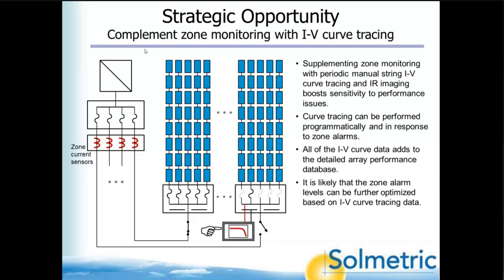There's another strategic opportunity with curve tracing that we're seeing more and more of opportunity for in large systems, which is that if you have monitoring at the zone level at your inverter, as shown on the upper left-hand side here, these little red symbols represent current monitors attached to each of the combiner box inputs or outputs, I should say, at the inverter, coming into the inverter. So your monitoring system will tell you how much current you have in each subarray. And it's really nice to complement that kind of zone level monitoring, that granularity, with IV curve tracing at the combiner box level, because it's so fast. You can blow through a combiner box in very, very little time.